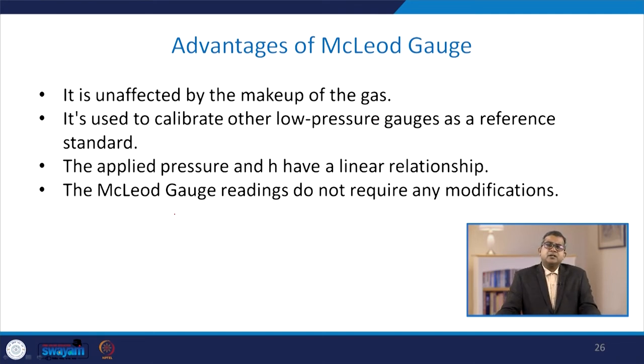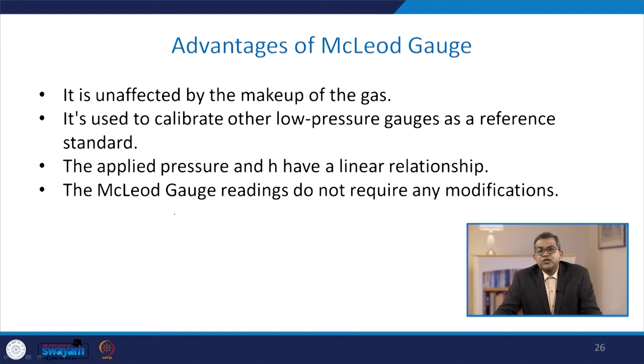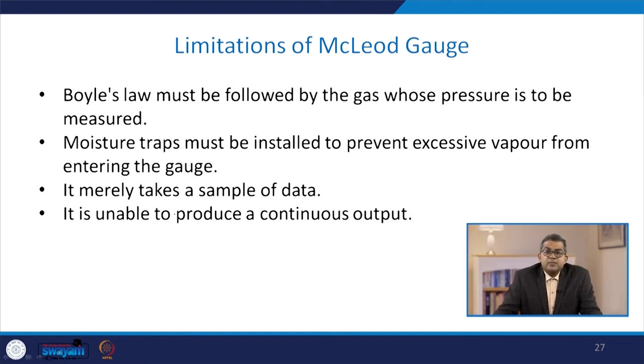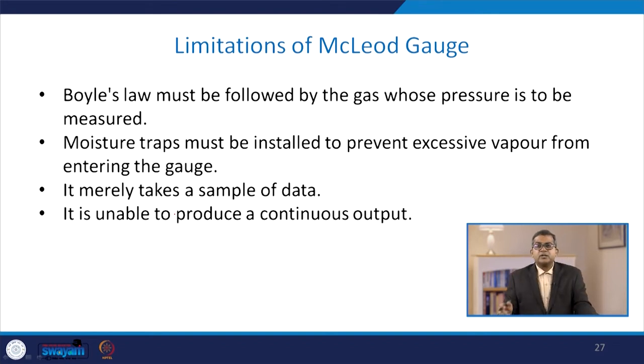Advantages of the Macleod gauge include: it is unaffected by the makeup of the gas; it is used to calibrate other low-pressure gauges as a reference standard; the applied pressure and h have a linear relationship; and readings do not require any modifications. Limitations include: the gas must obey Boyle's law; moisture traps must be installed to prevent excessive vapour from entering the gauge; it merely takes a sample of data; and it is unable to produce a continuous output.